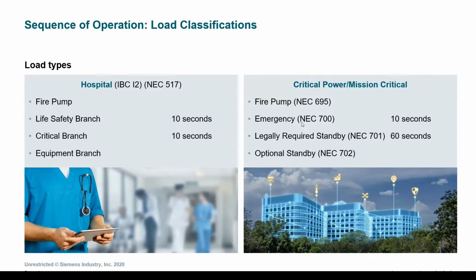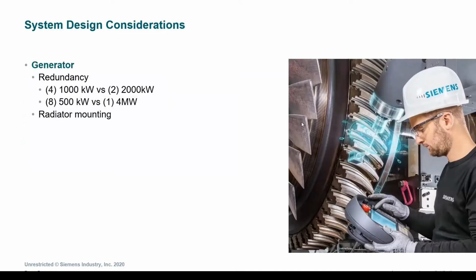And differentiating healthcare from non-healthcare, we'll talk about emergency as defined by NEC 700, legally required standby as defined by NEC 701, and optional standby. As Jeremy laid out, the sequence of operation identifies how the transfer switches and parallel switchgear operate and primarily come onto the emergency mode.